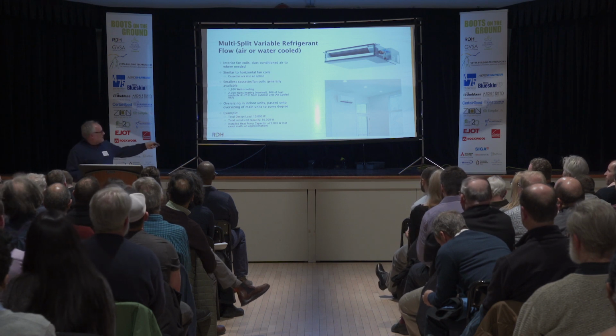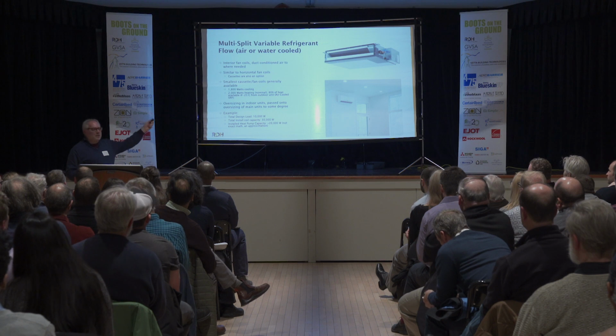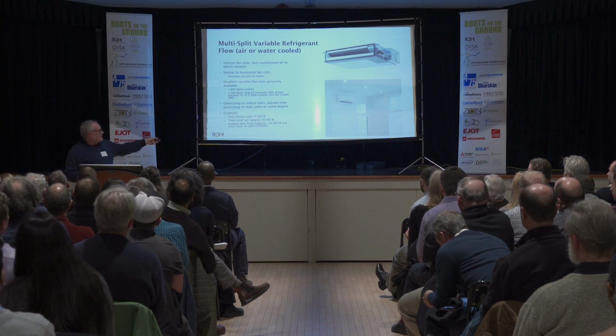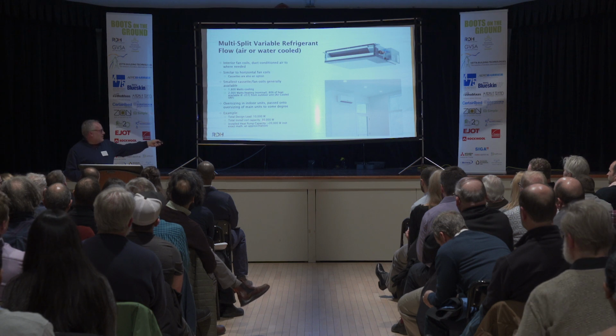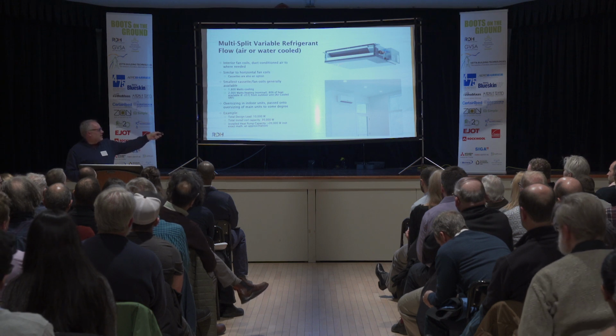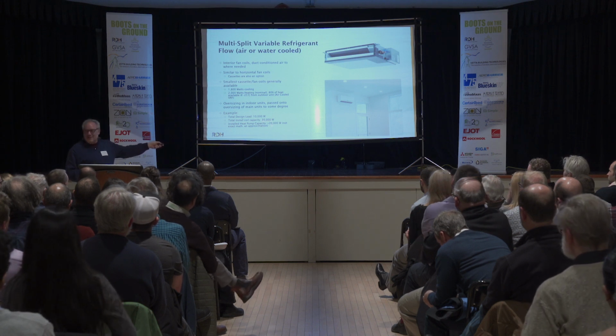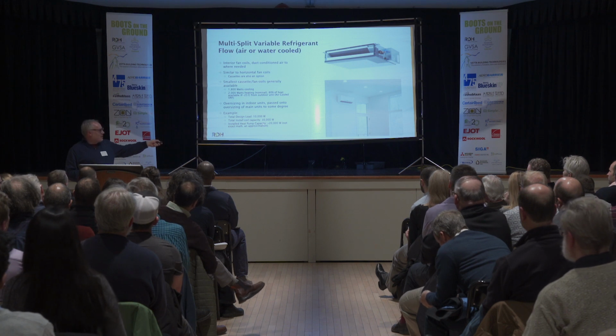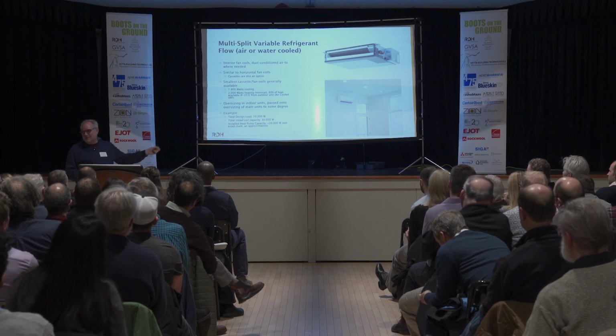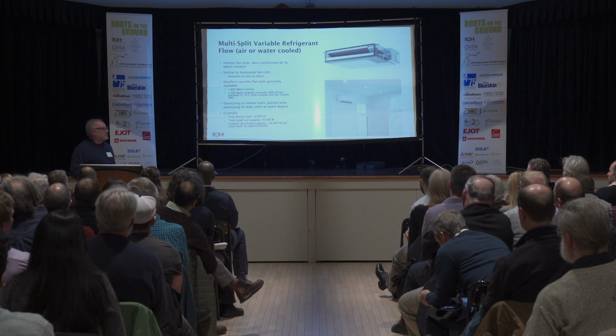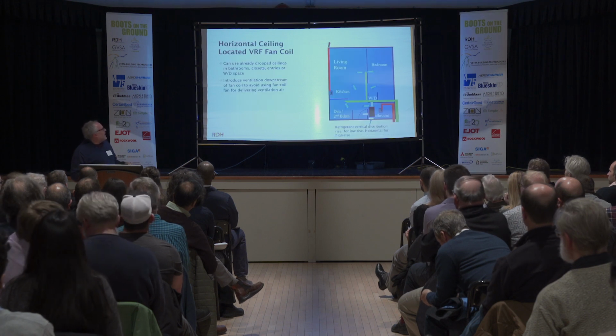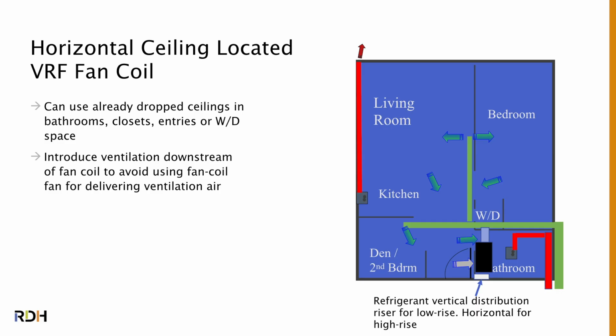So here's an example, a building with a total design load of 10,000 watts, but because we had to buy these larger units, we've installed 30,000 watts of these things. But the central heat pump I had to buy isn't 10,000, it's probably some number in between, like 20,000. So that's one of the challenges with VRF. Of course, the other challenge with VRF, and how you would locate it in the building, is kind of the same thing as the other fan coils.